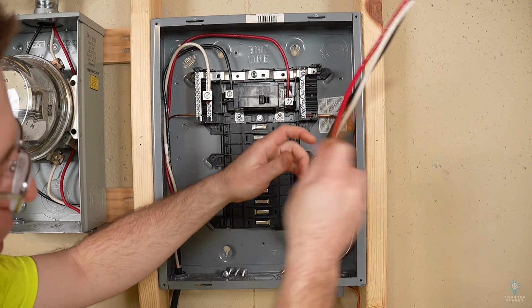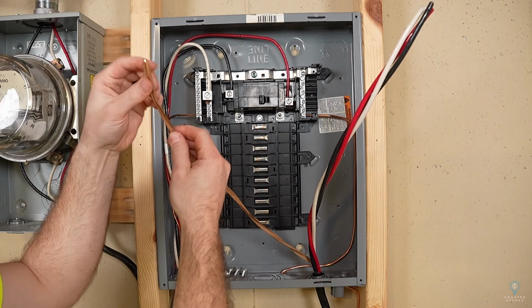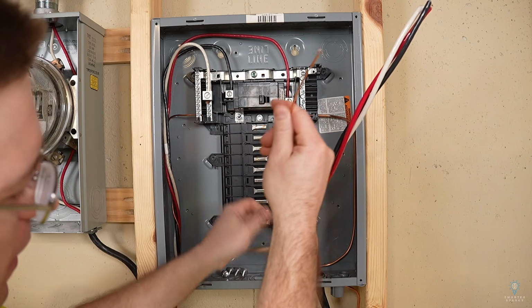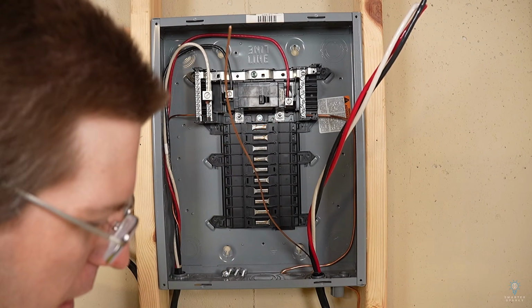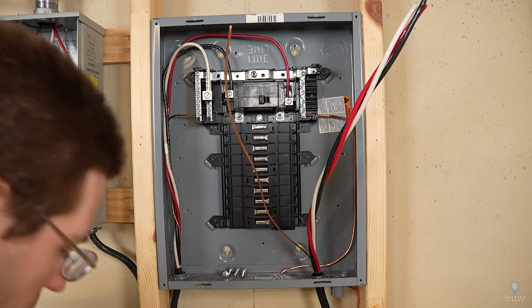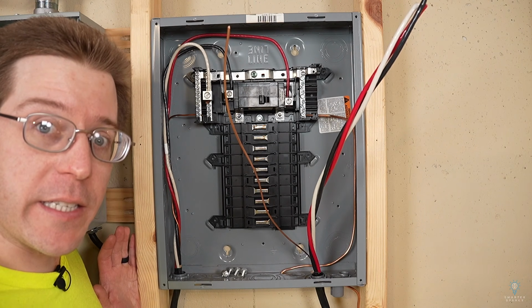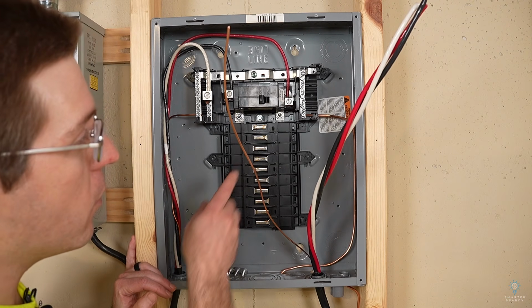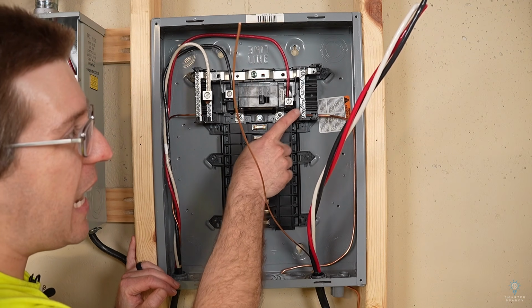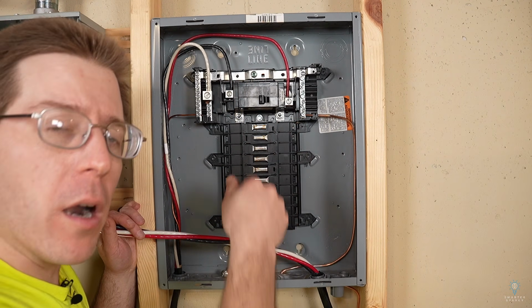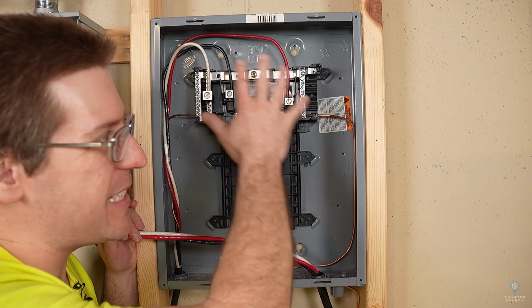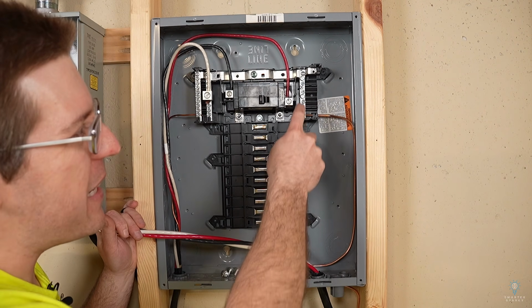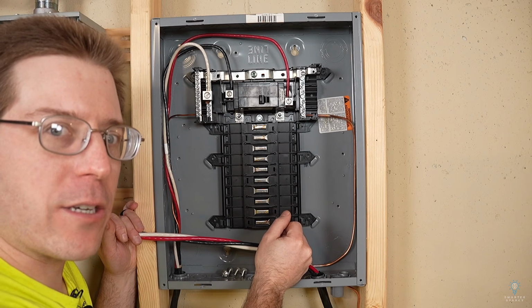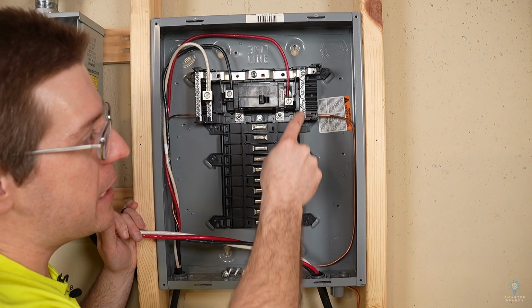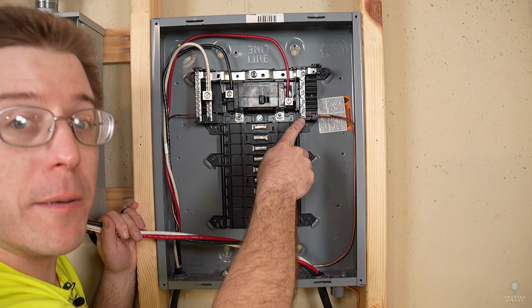So I'm going to separate everything here. This ground wire comes with this paper sheath on it, just like all NM does, and we'll peel that back. If you've got SER, it's going to have more of a plastic wrapping inside of there. Here's where things get a little different. Because this is the main electrical panel, we can actually land our ground and our neutrals on the neutral bar. Go check out the video I made explaining the insides of a main electrical panel, and I explain a tiny bit more detail why we actually share those in the main panel. Basically, in the main panel, the neutral and the ground bar can be shared, but in a sub panel, they have to be completely separate.